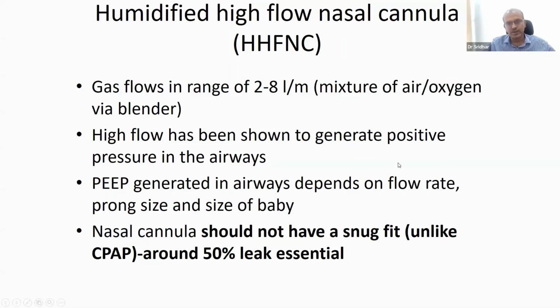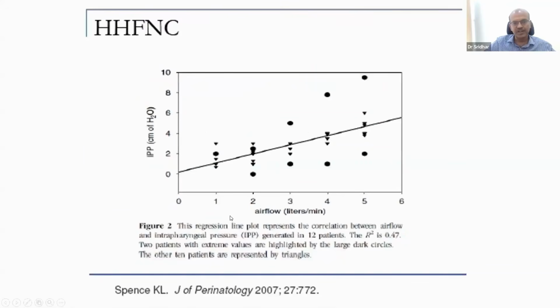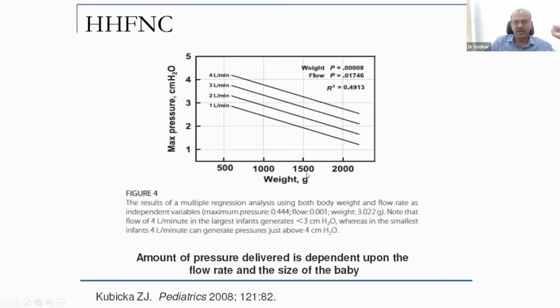High flow has been shown to generate positive pressure in the airways. The PEEP generated depends on the flow rate, the prong size, and the size of the baby. Obviously, the prong size should have a 50% leak and it should not have a snug fit. So there are a few studies which have looked at the comparison of the airflow with the pressure delivered in the airway, and in the same size of baby, as you increase the flow, the pressure goes up. But as you can see here, according to the size of the baby, the pressure varies. So in a 500 gram baby, a flow of 4 liters can reach 4 centimeter pressure, while in a bigger baby, a 4 liter flow can give 2.5 to 3 pressure. So obviously, the size of the baby matters. It's related to the Laplace law, where the leak is going to depend on the size of the nostril and the leak around it.